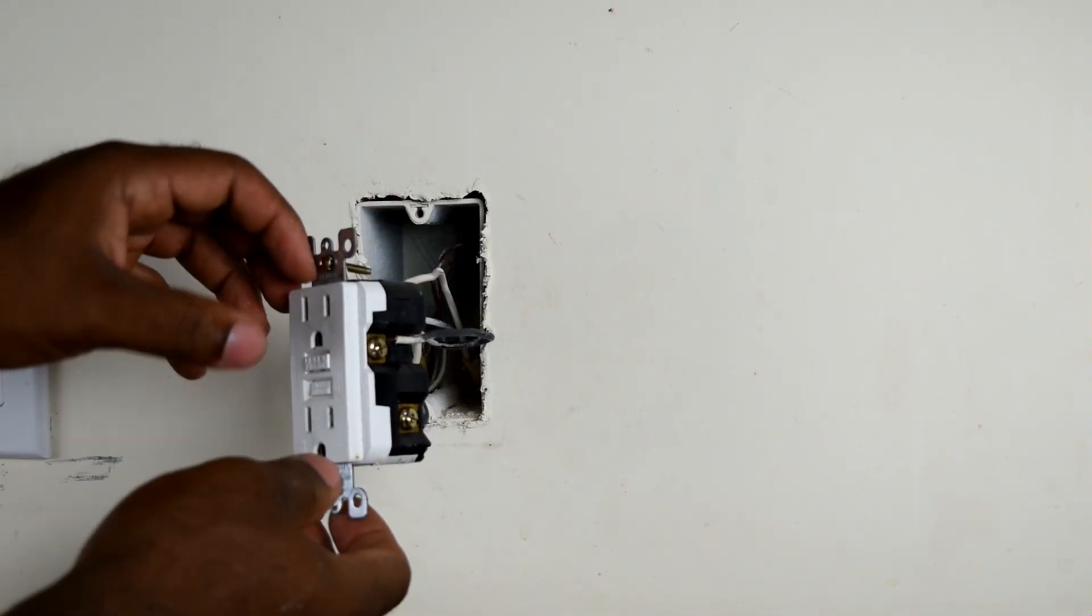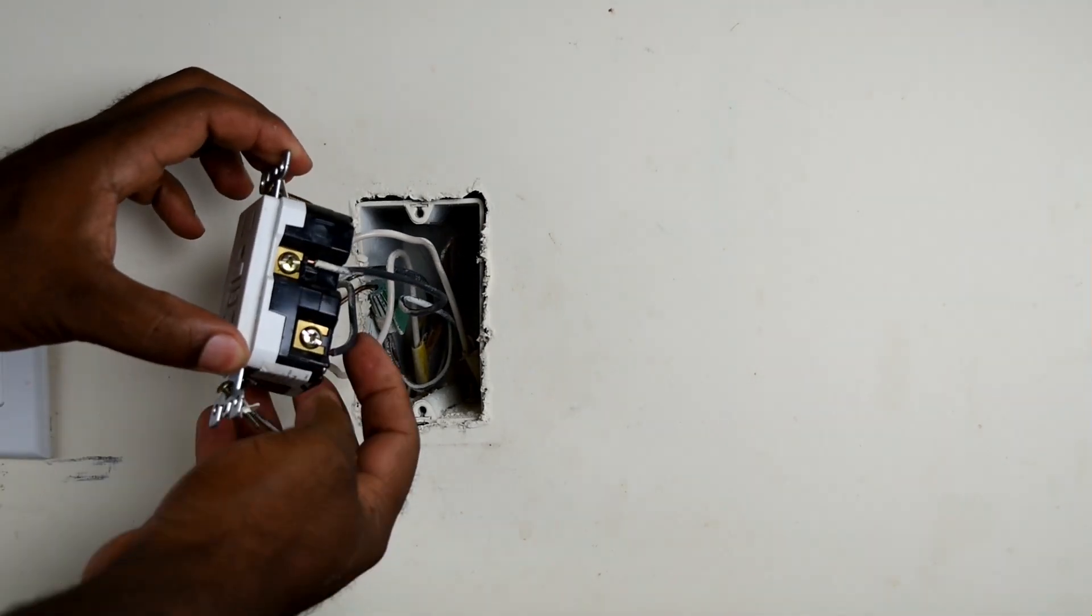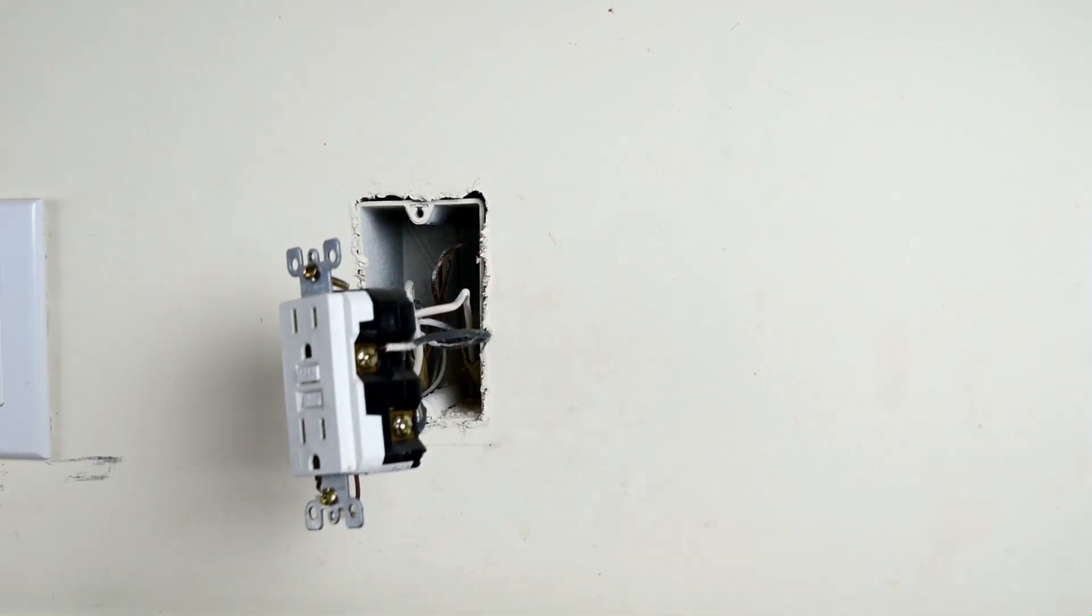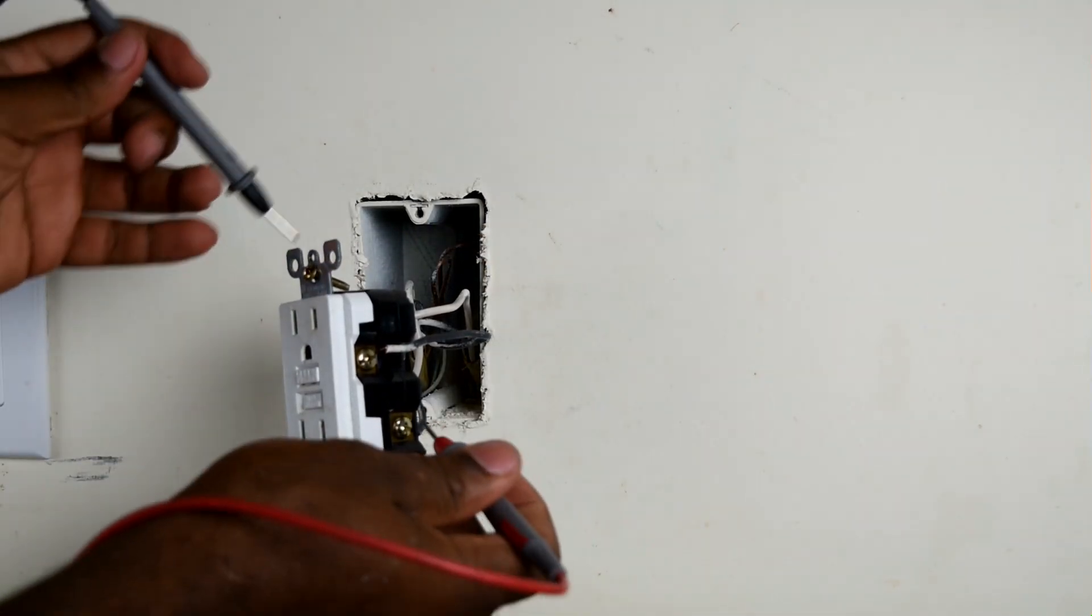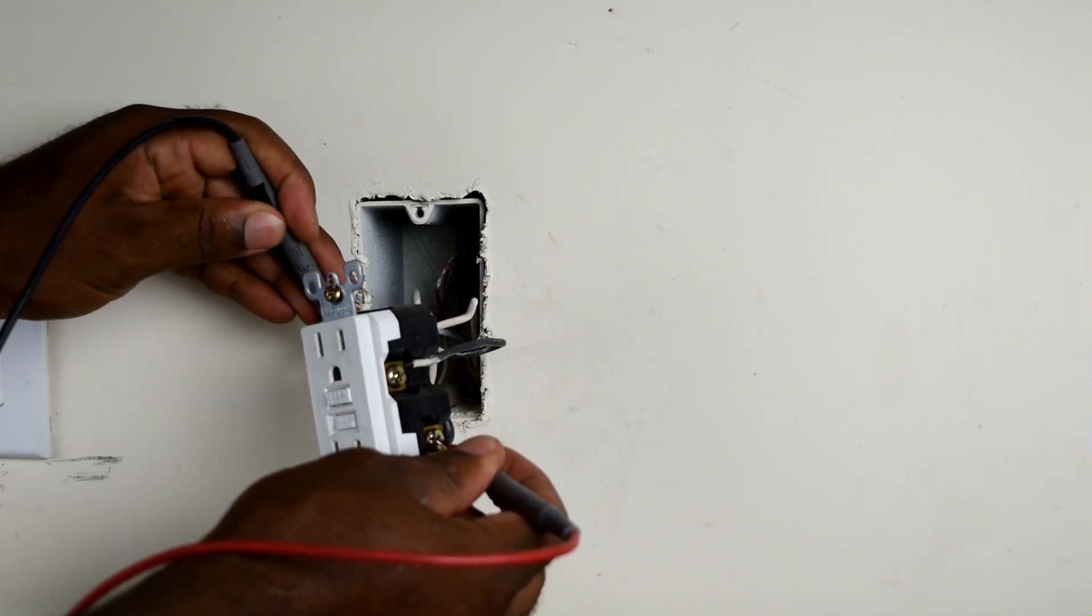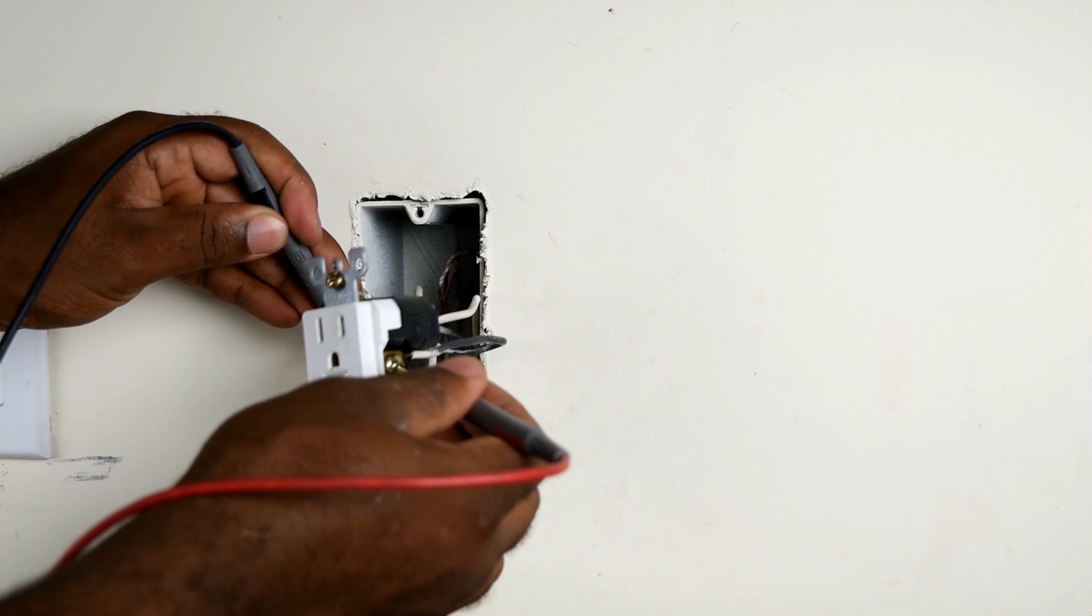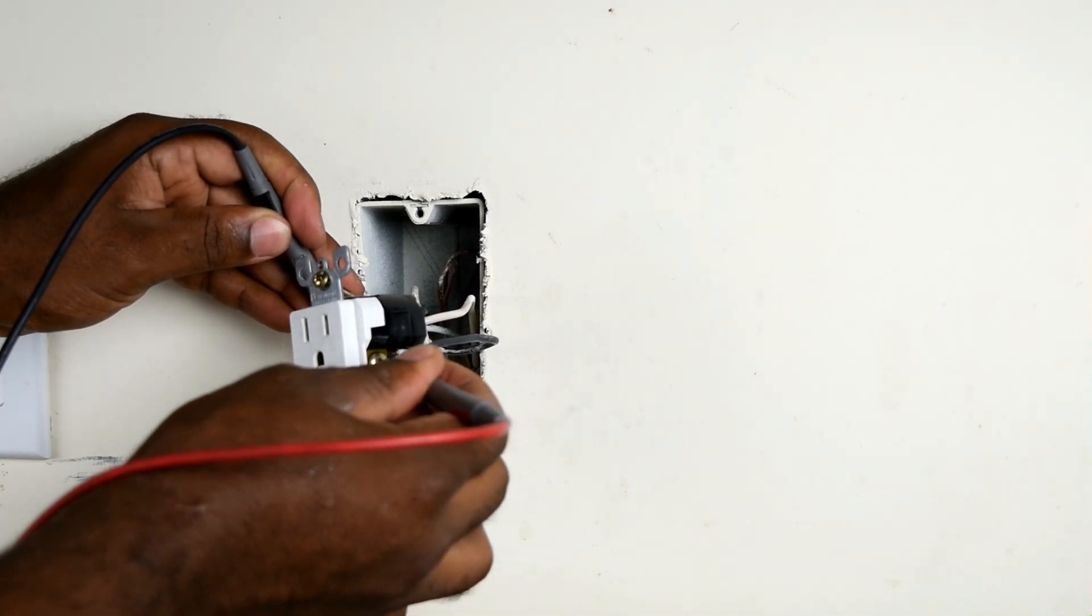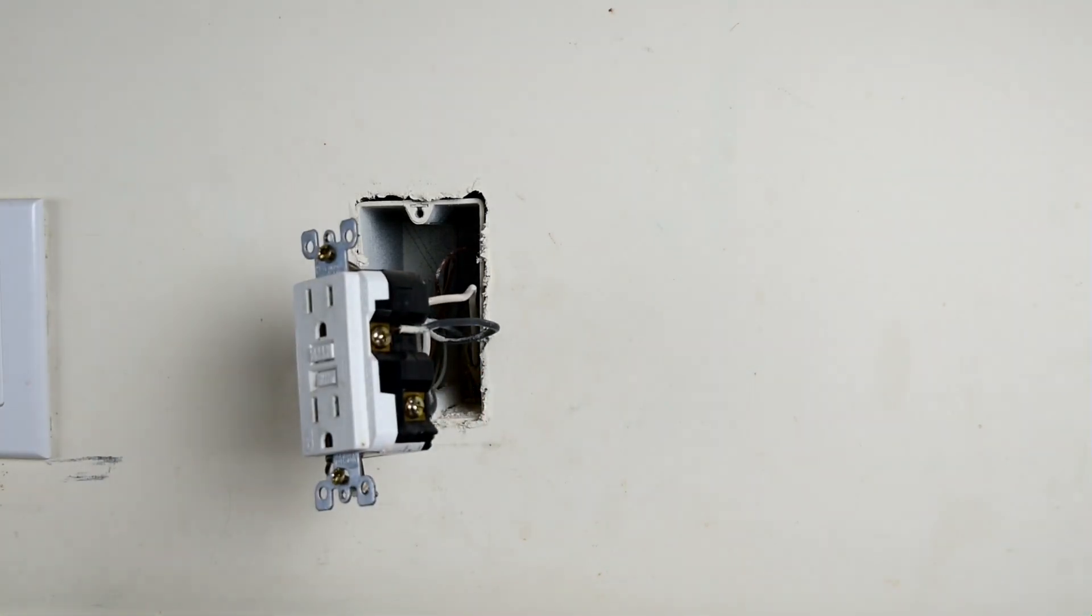You can pull all this off. As I said, I know which one my line is. My line is here and this is my load at the top. I should have some kind of voltage on my line even though it's low. I'm around four volts, and if I check my out I should have nothing and that remains accurate.